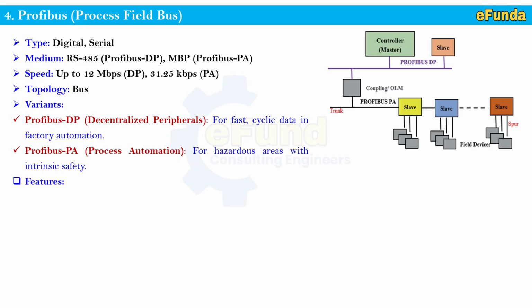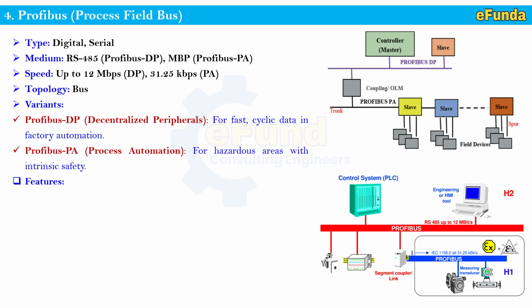Before that, one can see the detailed architecture where the field devices are connected with the help of Process Field Bus, as you can see in the second picture where the H1 and H2 are shown, and then how field devices are connected to the segment coupler via the link of a Profibus where measuring transducers are shown, and then further extended to the control system.